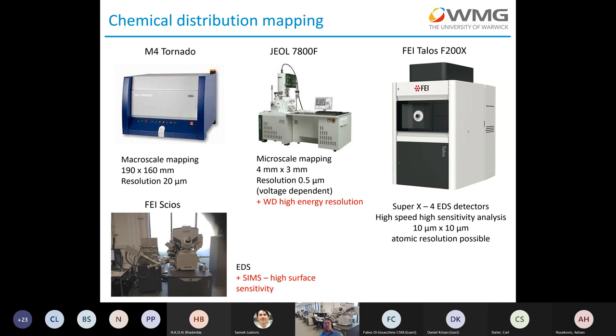One advantage of the TEM is that, as a higher voltage instrument, it gives a larger analytical range than the SEM, so some peak overlap issues in SEM can be resolved simply by looking at higher energy characteristic lines. In addition, we have a SIMS attached to a dual beam, which can combine much higher spatial resolution than EDS in the SEM with much higher surface sensitivity.